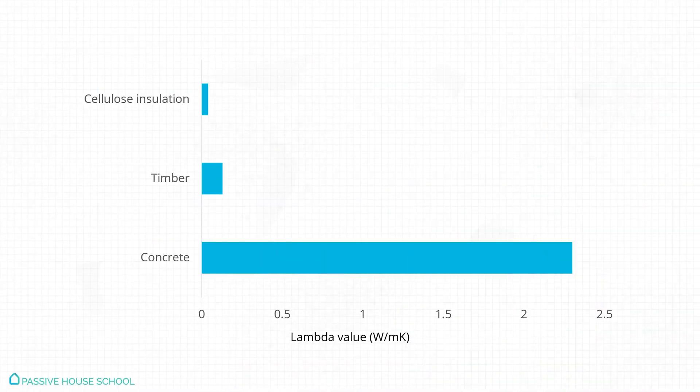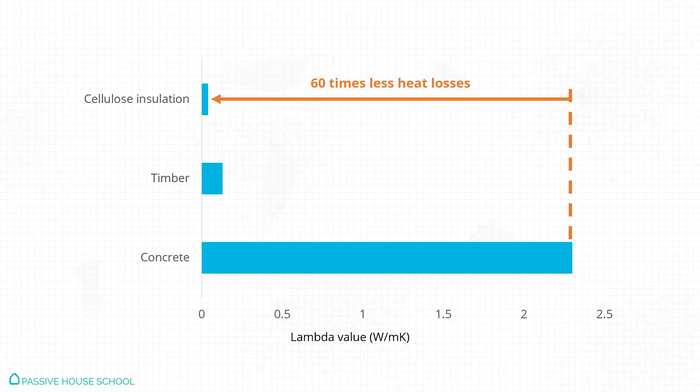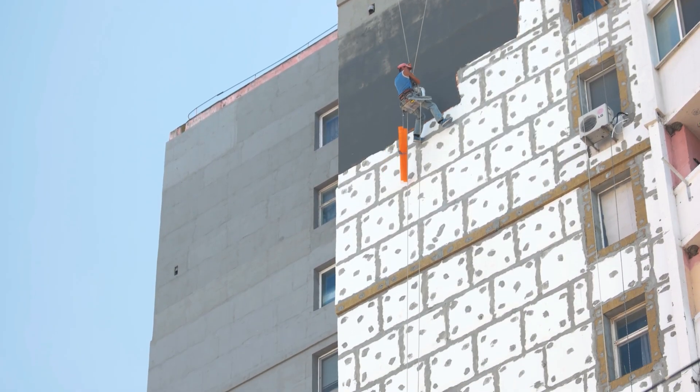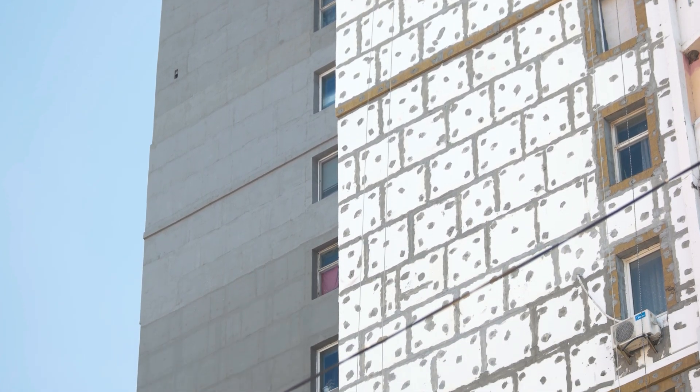Lambda values are essential when comparing insulation qualities of different materials. For example, concrete has a lambda of around 2.3 watts per meter Kelvin, timber has 0.13 watts per meter Kelvin, and cellulose insulation has a lambda of around 0.04 watts per meter Kelvin. So we lose almost 60 times less heat through cellulose insulation compared to concrete, and three times less than timber. This principle also applies when comparing different types of the same material, such as expanded polystyrene — EPS — where various products on the market each have slightly different insulating properties, and lambda values let us determine which offers better performance.